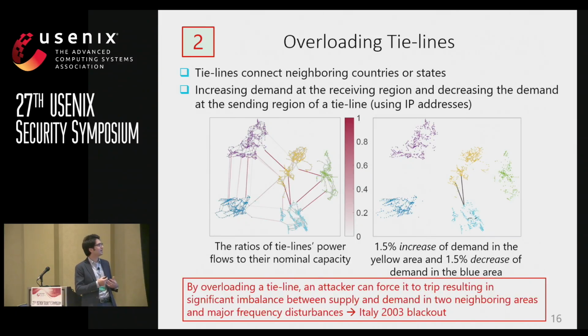After such a failure, this can result in a huge imbalance between power supply and demand in both areas and trigger a frequency stability problem or another set of cascading line failures. If you look at the history of blackouts, it is somewhat similar to the scenario that happened in Italy in 2003, that started with a failure in a tie line, and soon the initial failure triggered other failures in other tie lines in Italy that resulted in a larger scale blackout at that time.